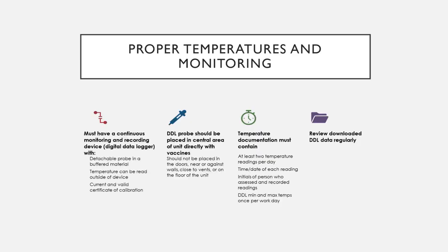So proper temperatures and monitoring. You need to have a continuous monitoring system, which is used with the DDL, the data logger. There needs to be a detachable probe in a buffered material. The temperature must be able to be read from the outside, and the certificate of calibration must be current and valid. We've noticed that DDLs with an expired certificate of calibration tend to start not reading accurately anymore.